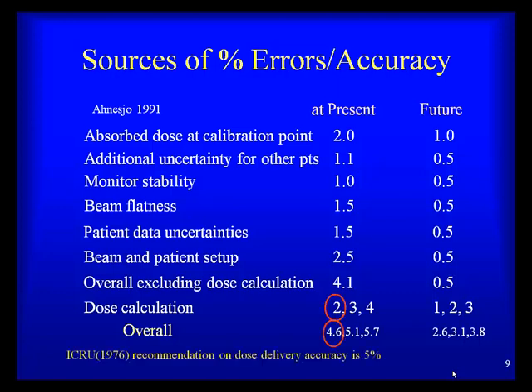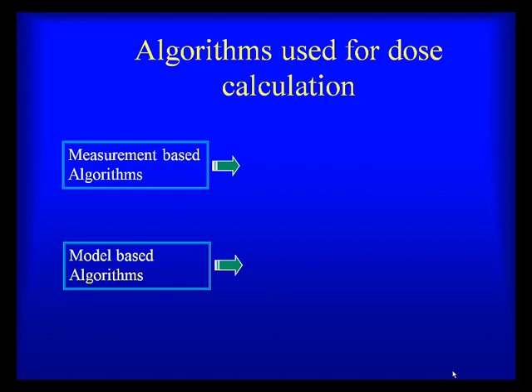Looking at different sources of errors in radiation therapy delivery, to achieve less than 5% overall accuracy of delivery, we need a dose calculation algorithm that is better than 2% accurate. If we hope to deliver radiation with less than 3% error, the corresponding accuracy required in dose calculation is 1%. So we need to strive to develop as good a dose calculation algorithm as possible.